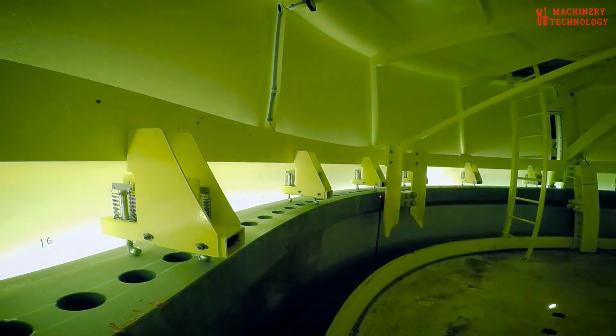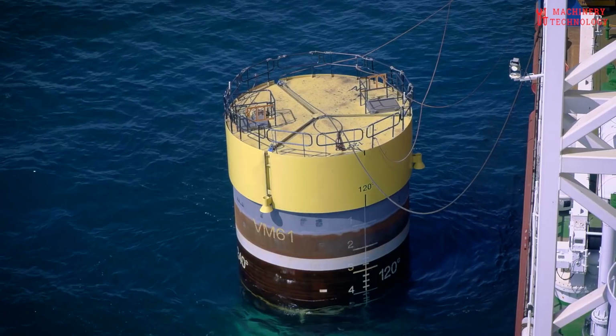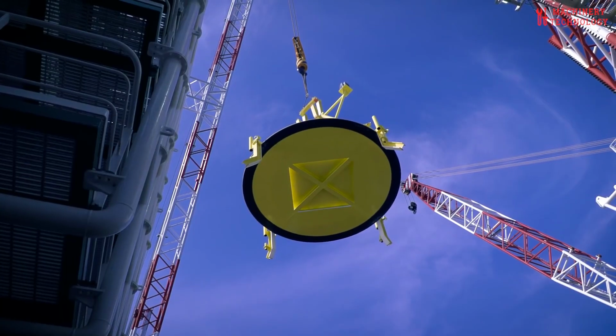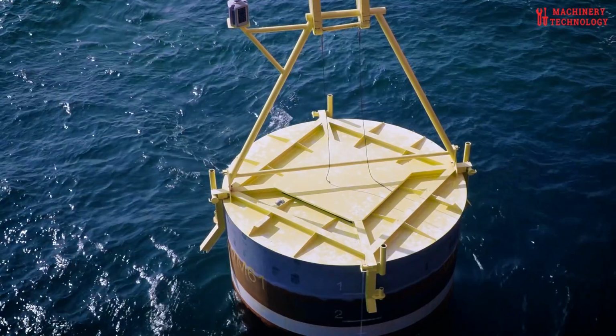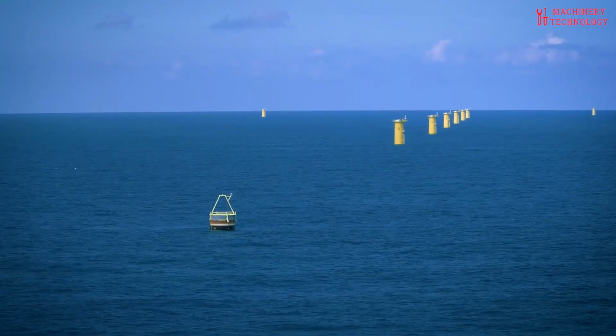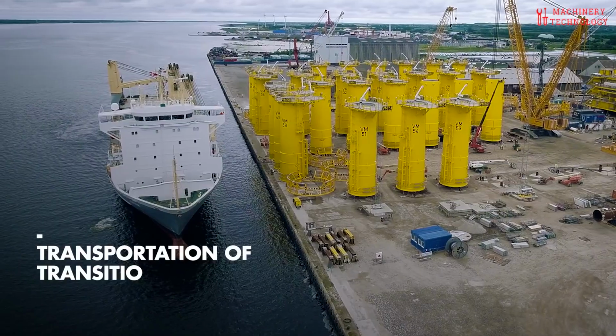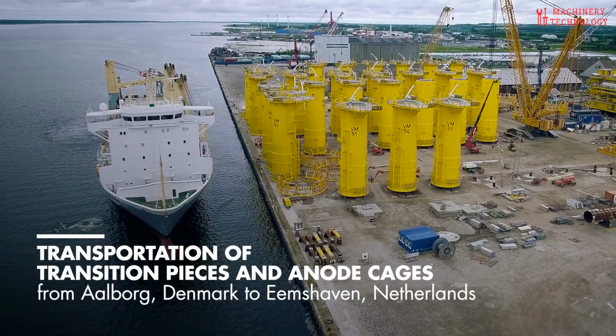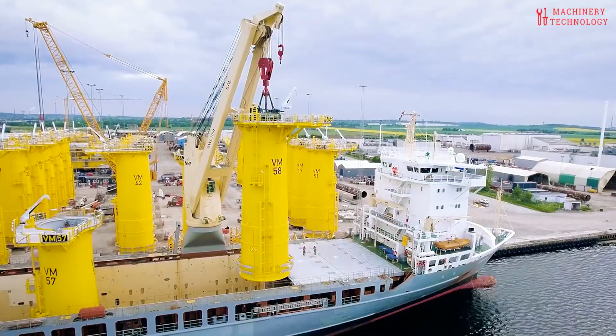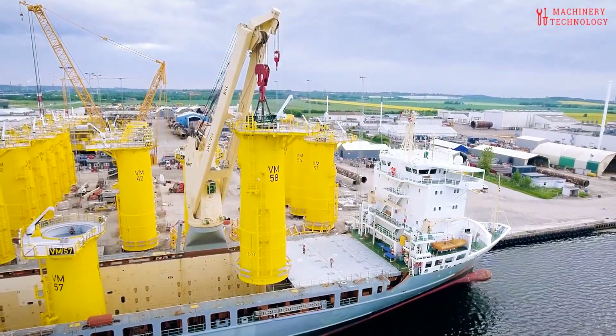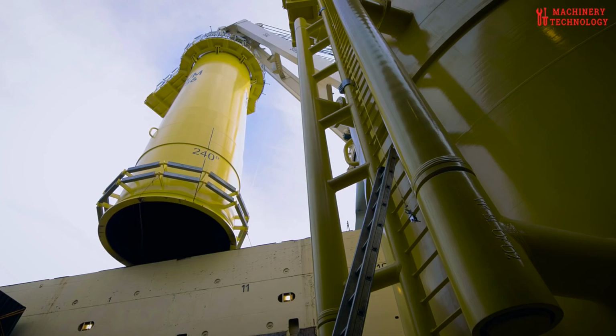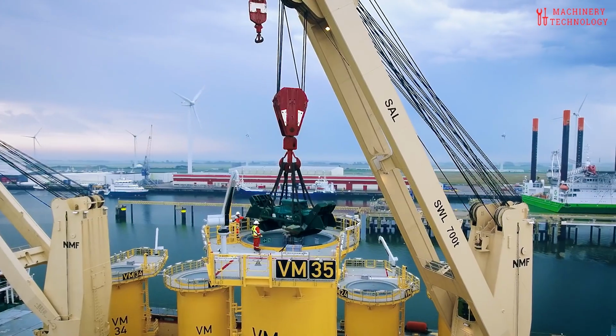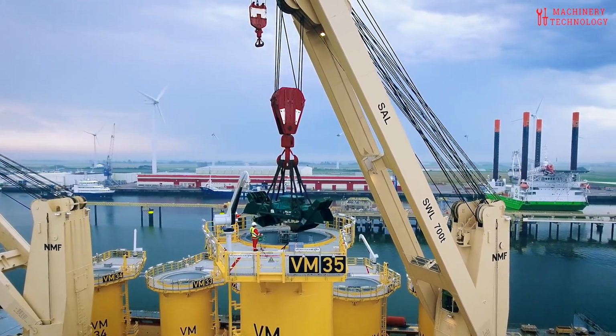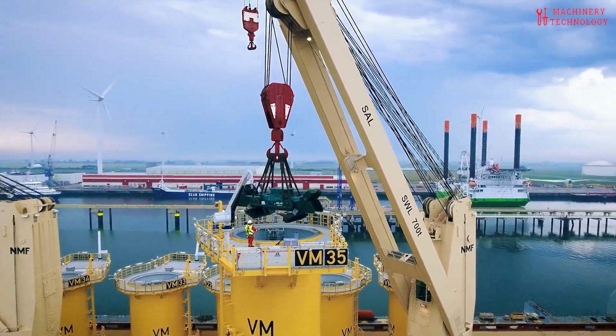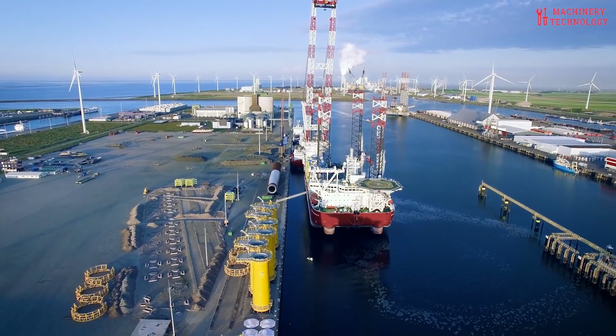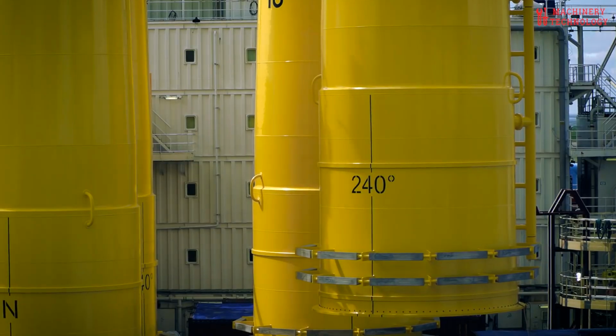For electrical transmission, high-voltage alternating current (HVAC) is typically used for shorter cable routes under 80 kilometers, as it is more economical and simpler to install. However, for distances beyond 80 kilometers, high-voltage direct current (HVDC) transmission becomes the preferred choice due to its superior efficiency over long distances. Unlike HVAC, HVDC systems minimize power losses by reducing reactive power transmission, allowing efficient energy transfer over extended routes. HVDC is thus ideal for offshore wind farms located far from the shore.